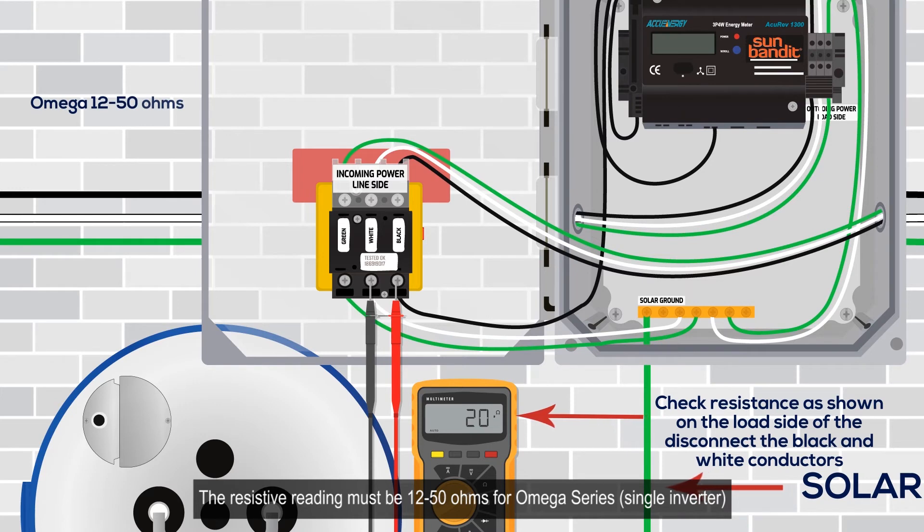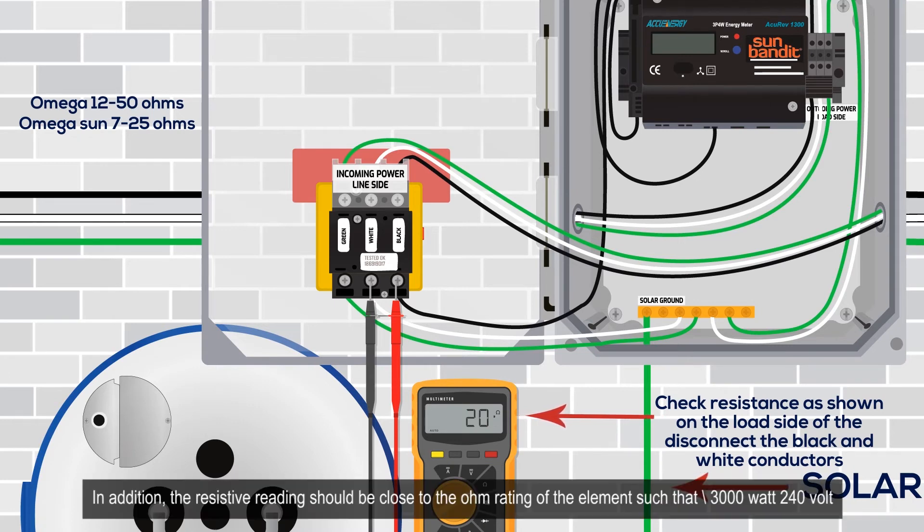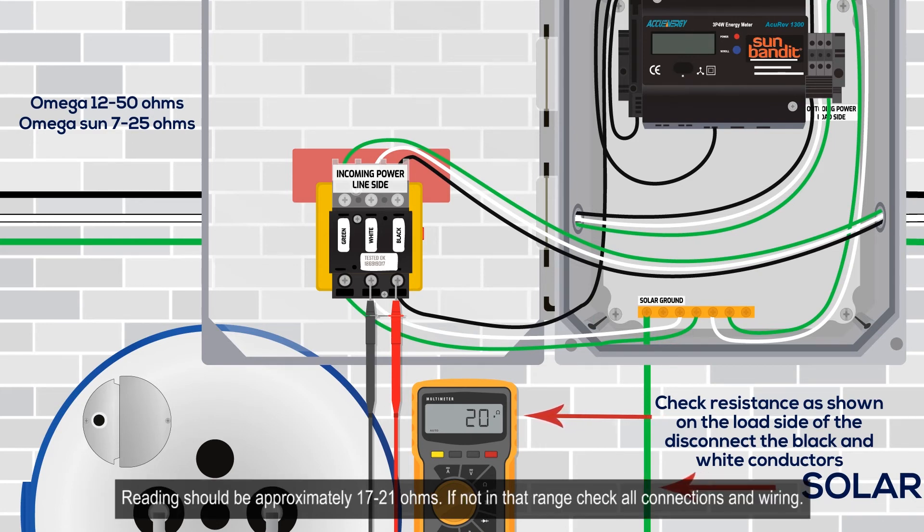The resistive reading must be 12 to 50 ohms for a Omega Series single inverter, or 7 to 25 ohms for a Omega Sun dual inverter system to operate. The resistive reading should also be close to the ohm rating of the element — for example, 3000-watt, 240-volt Sun Bandit elements are 19.2 ohms nominal, so readings should be approximately 17 to 21 ohms. If not in that range, check all connections and wiring.